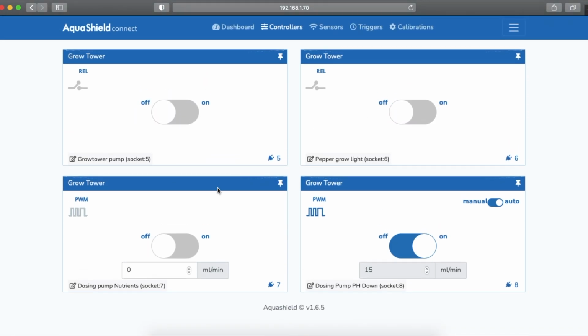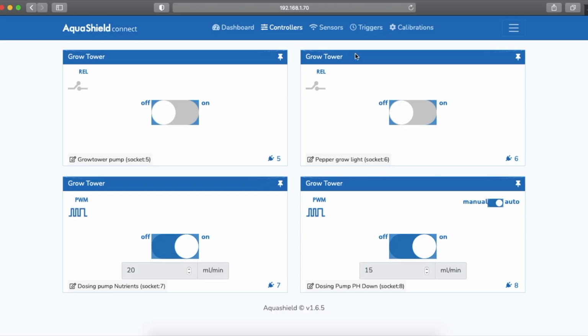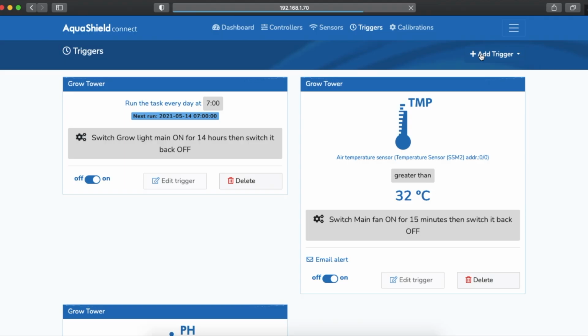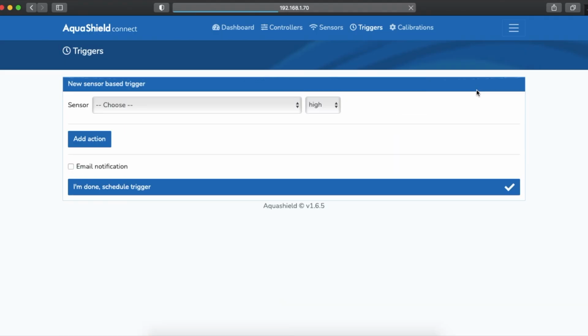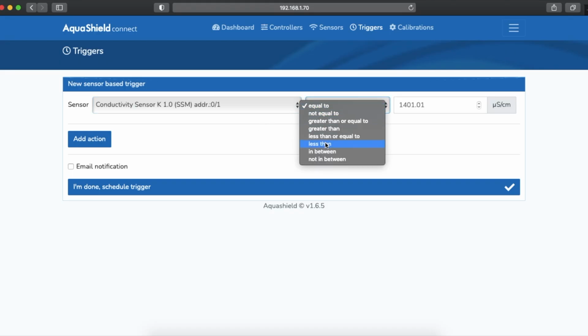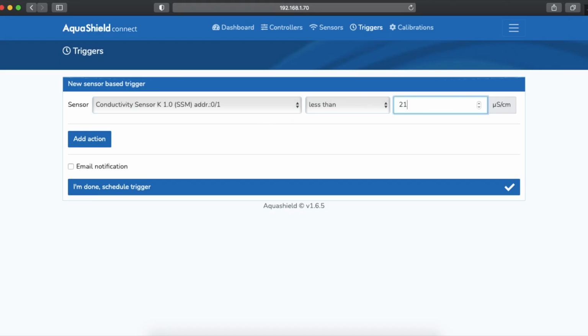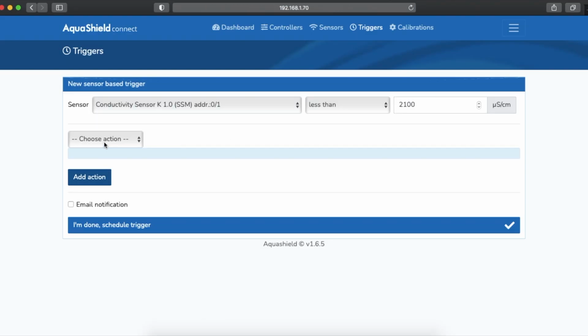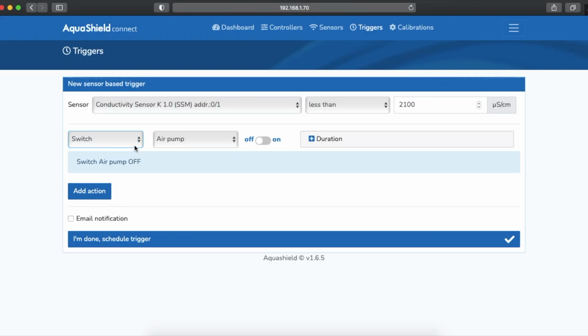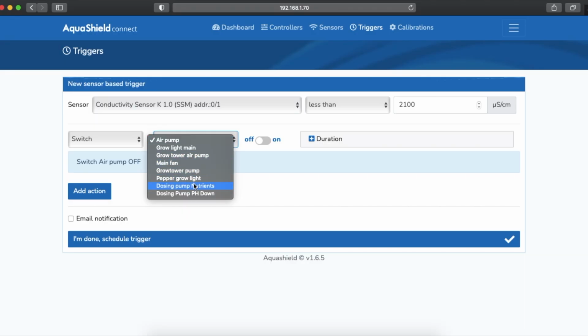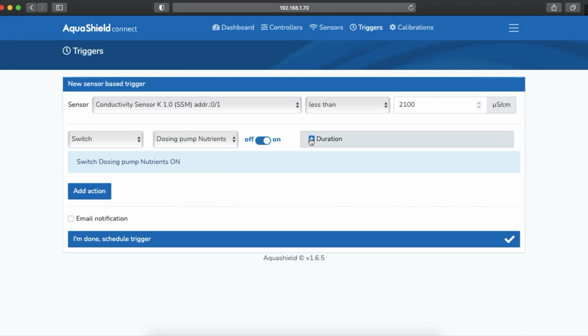Similarly to this, we set the second dosing pump to add 20 milliliters of complex nutrients to the system per minute. After this, we created a sensor-based trigger to run every hour and check if the EC is lower than 2100 microsiemens per centimeter. If this is the case, the trigger will run for 60 seconds and add 20 milliliters of nutrients to the tank. As before, I also added an email alert to the trigger.